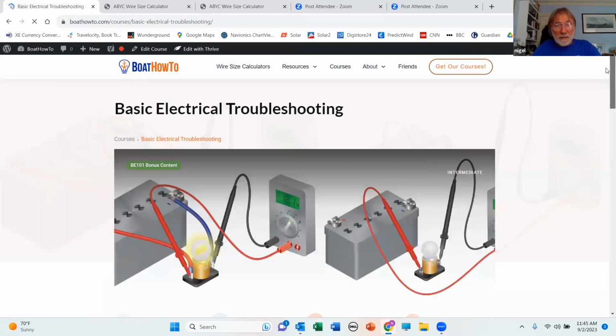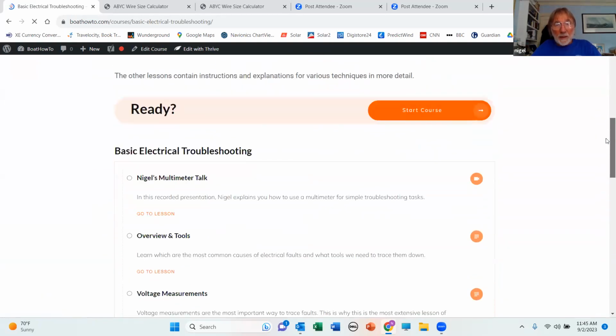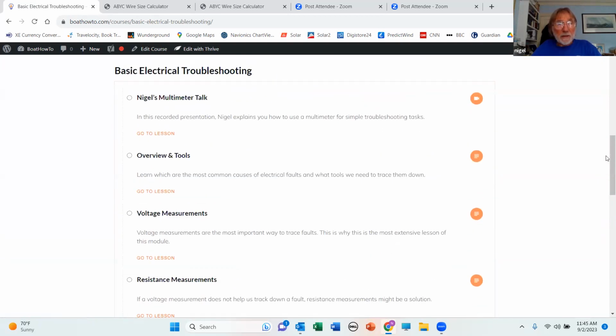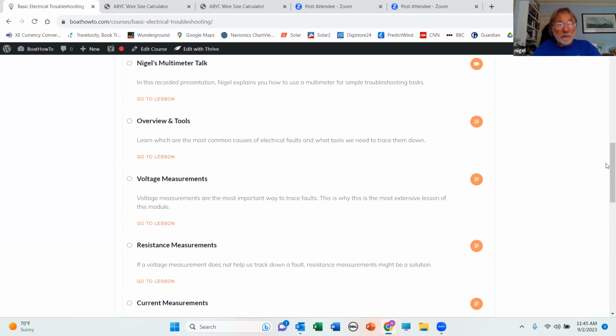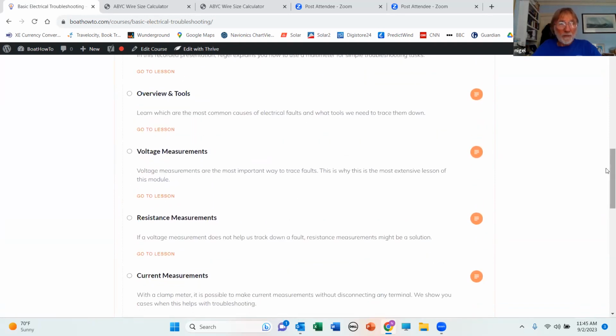First thing you need is a decent meter. And I'm not sure if I have any slides on meters. No, so not easily accessible. They're buried in there. You want to be able to measure voltage, AC and DC. And that actually, for simple troubleshooting, is all you need. When we get into other measurement modes, such as resistance, ohms, and even amps, some meters you can measure amps through the meter up to 10 amps.